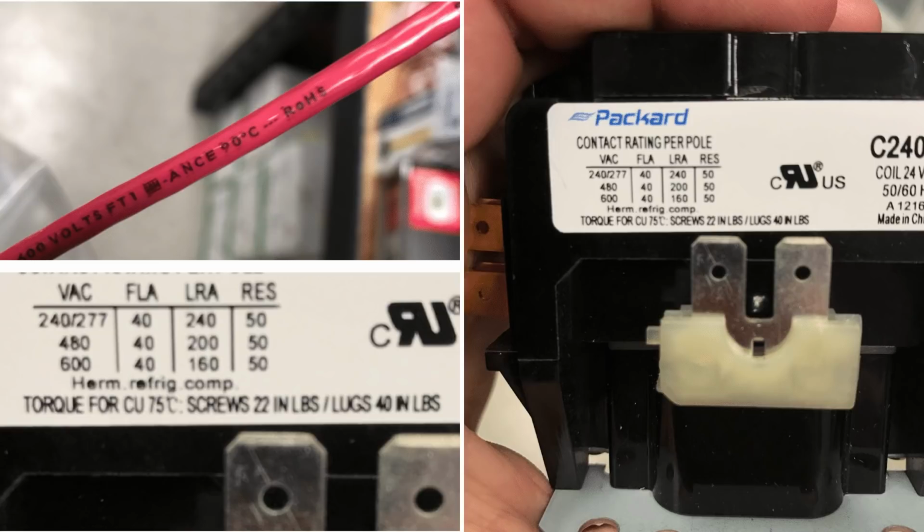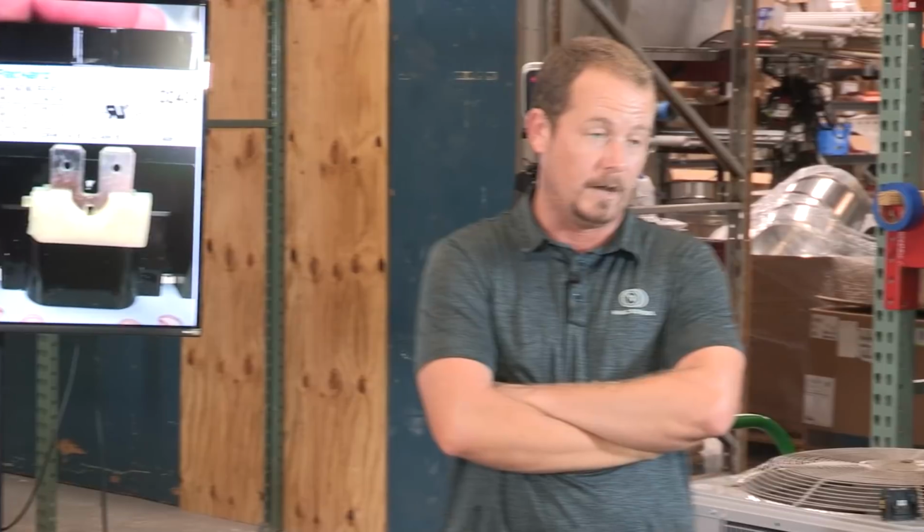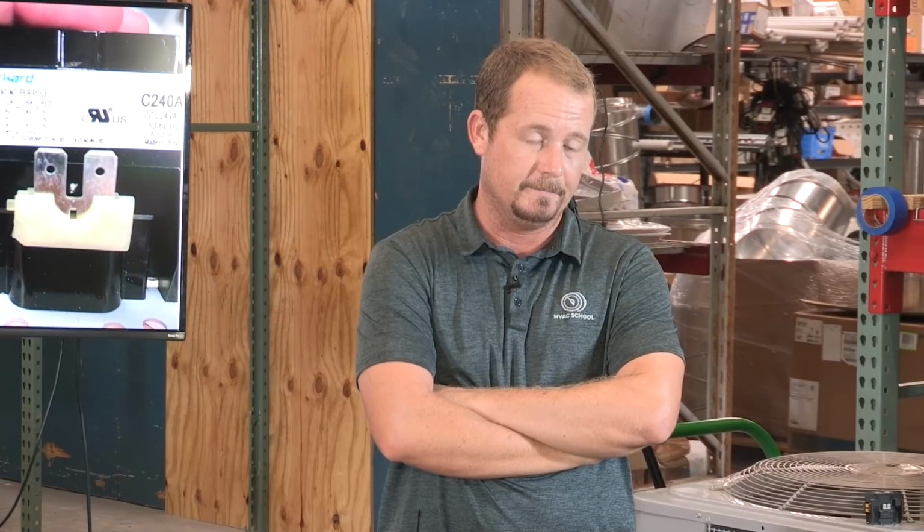So same thing. This is just a zoomed out view, just showing the same thing. But look up here at this conductor. What does it say on it? 90 degrees. So let's say we had these conductors connected to an appliance, but you were terminating them at this contactor, meaning you were connecting the high voltage conductors to the bottom of a contactor, which is often what we do. What is the Celsius rating of that circuit now?